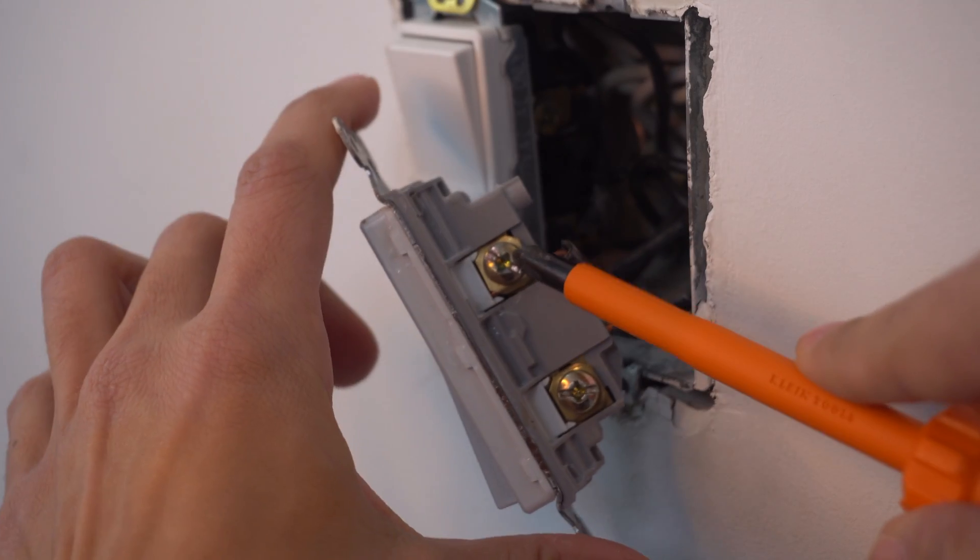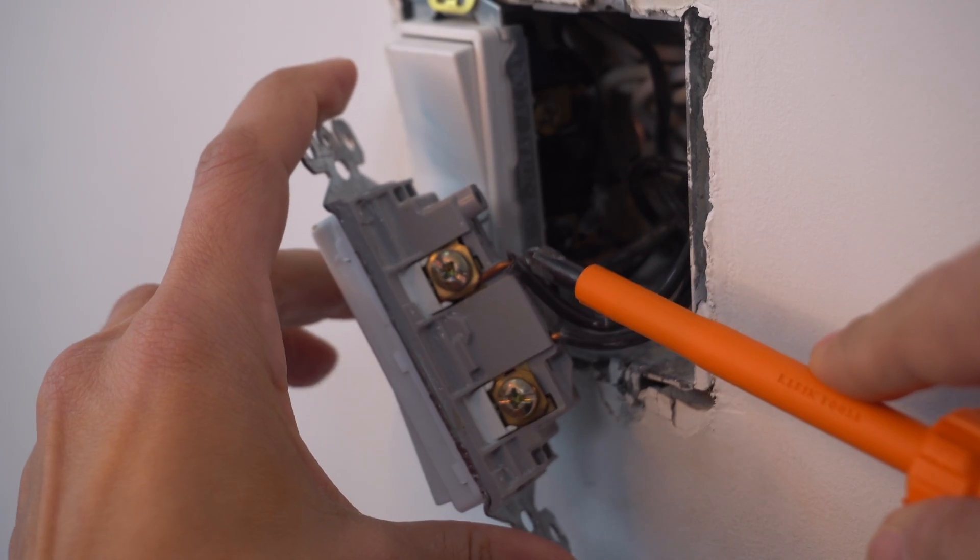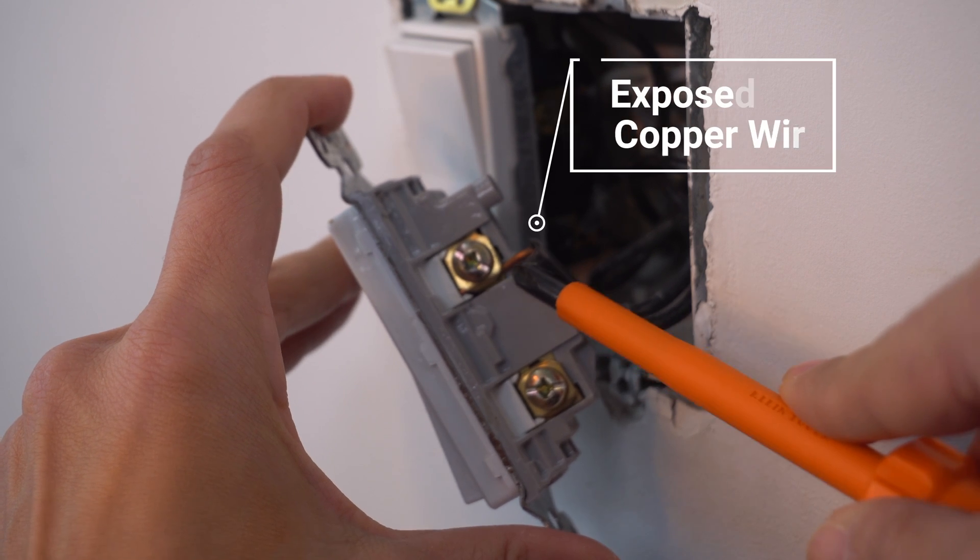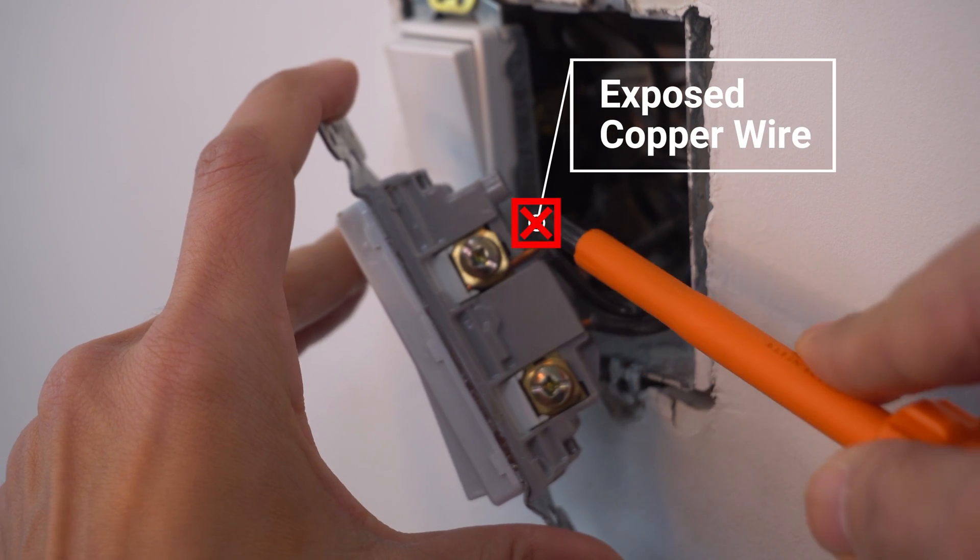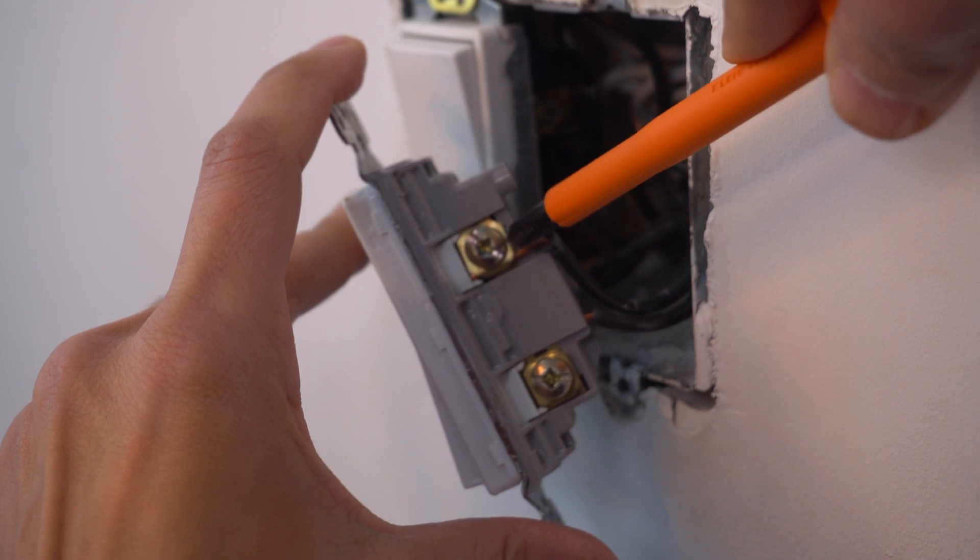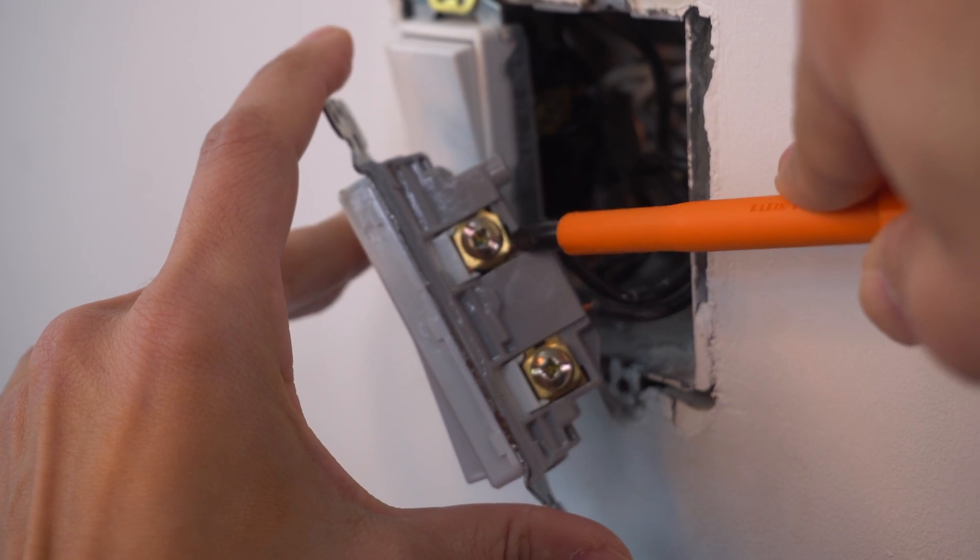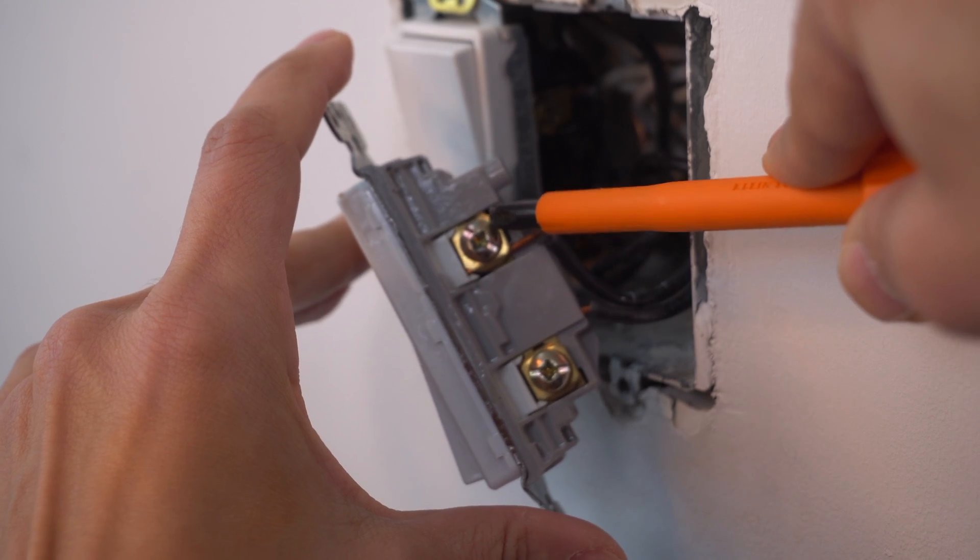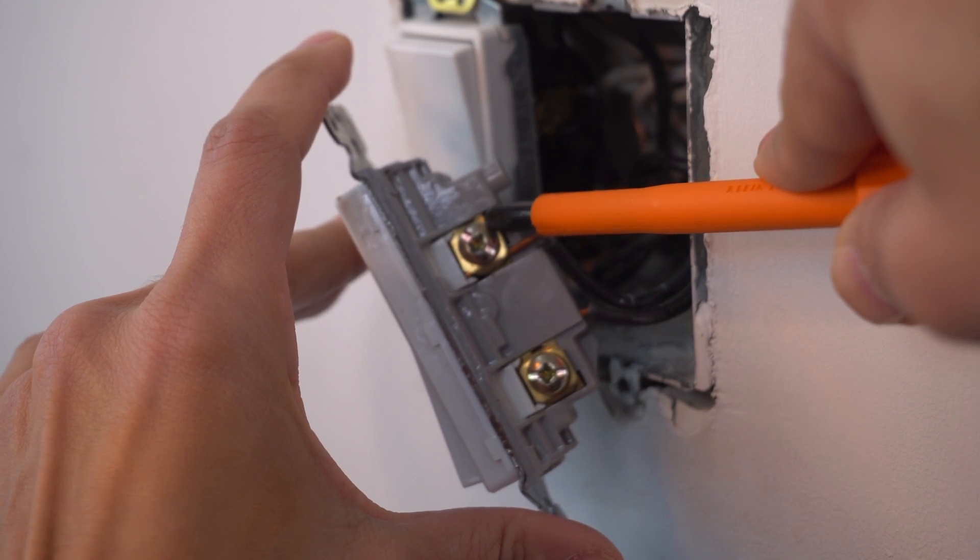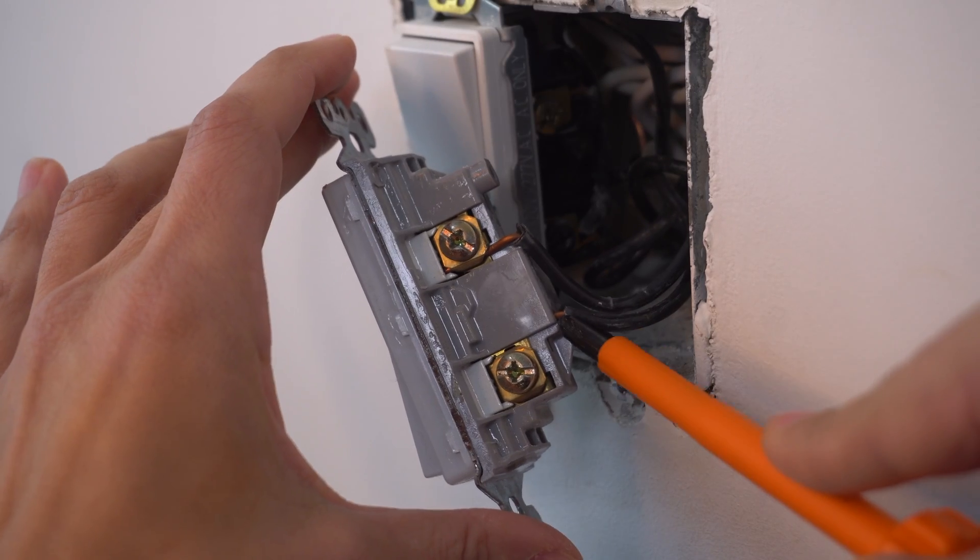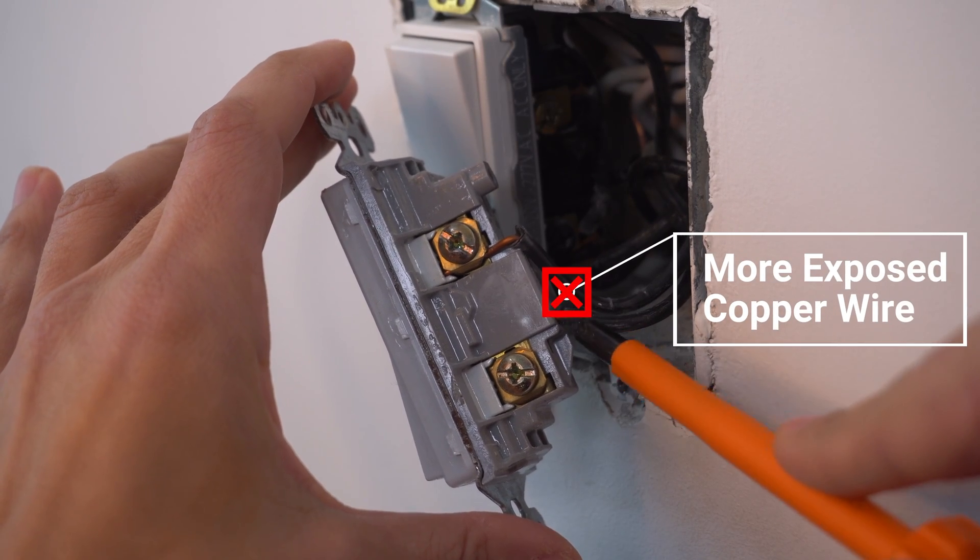Let's take a look at our terminal screws here. Already we have three huge problems. You do not want to see any exposed copper wire here with a terminal screw. You want this sheathing or insulation to be right up where this clamp is. This wire can also wrap around your terminal screw and make a J hook. That would have been a safe connection. Also, we have exposed copper here.